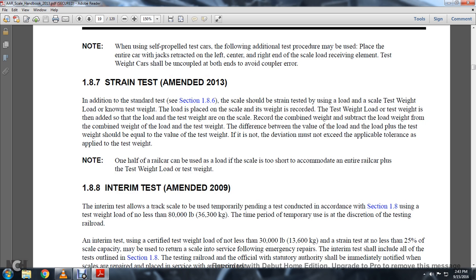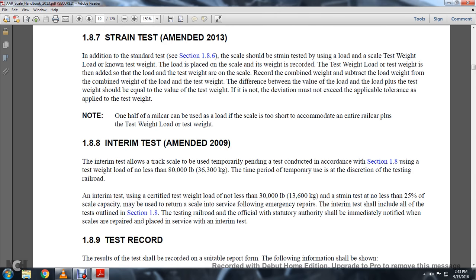1-8-7: Strain Test, Amended 2013. In addition to the standard test of Section 1-8-6, the scale should be strained. The strain test uses a load placed on the scale along with the test weight. The load is placed on the scale, and its weight is recorded. The test weight is then added to the load on the scale. Record the combination weight and subtract the load weight from the combined weight. The difference between the value of the load and load plus the weight should be equal to the value of the test weight. If not, the deviation must not exceed the applicable tolerance applied to the test weight.